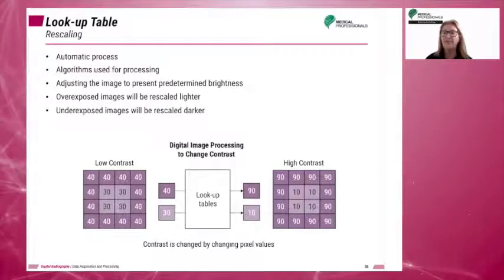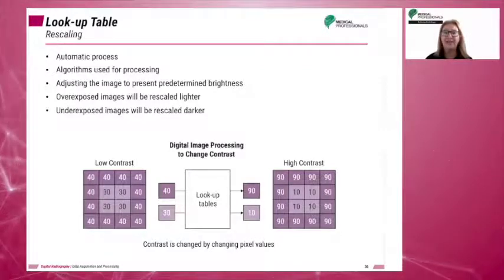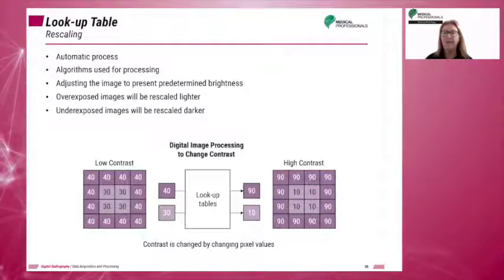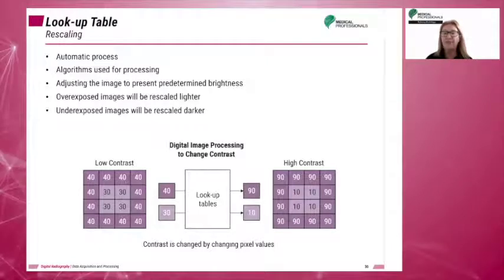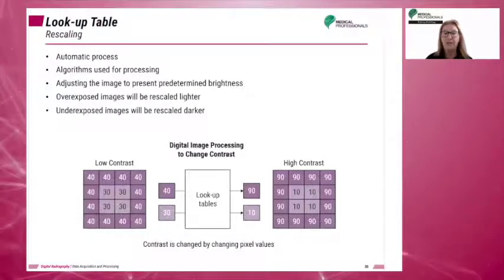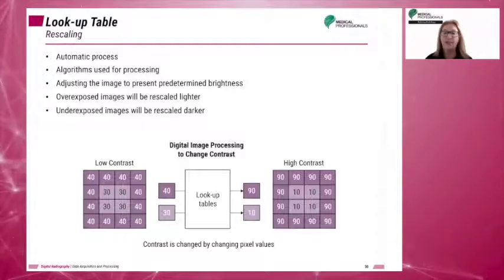The process of matching the captured image to a standardized set of values is called automatic rescaling. Automatic rescaling permits consistent output of image data and image display appearance even if exposure errors occur. Rescaling provides an acceptable image, but because the visual cues we are accustomed to are missing with digital imaging, rescaling the image pixel values can lead to overexposing a patient.